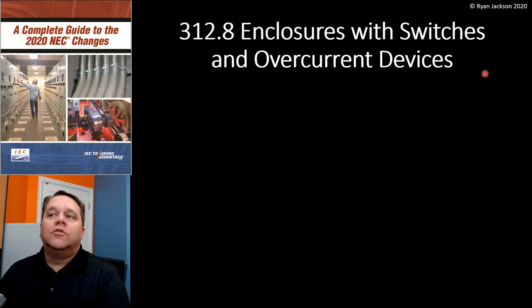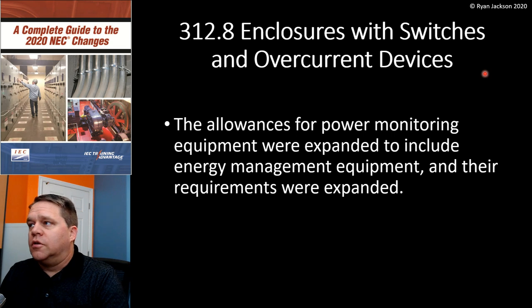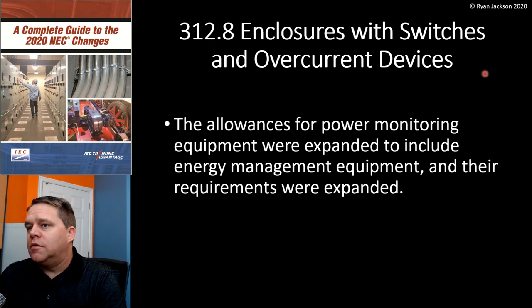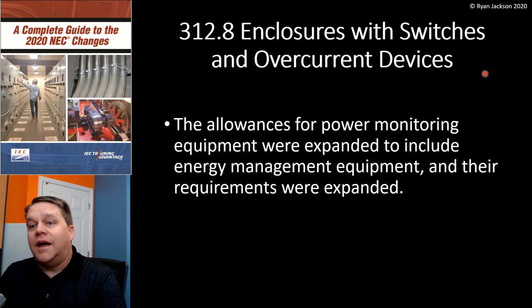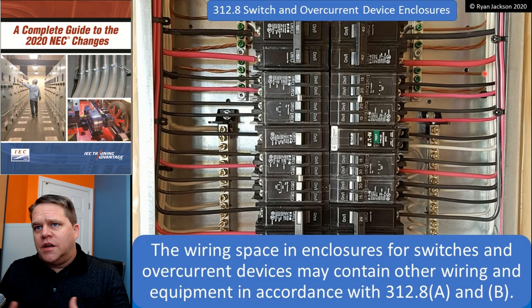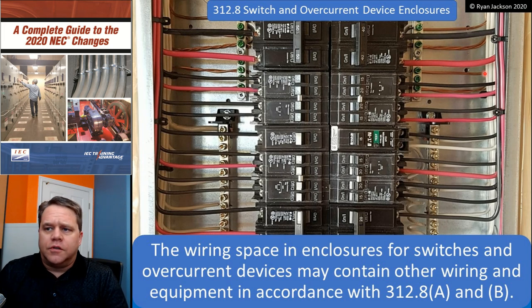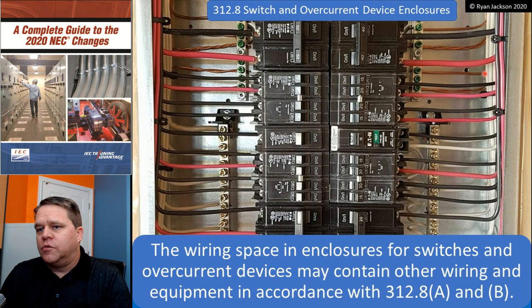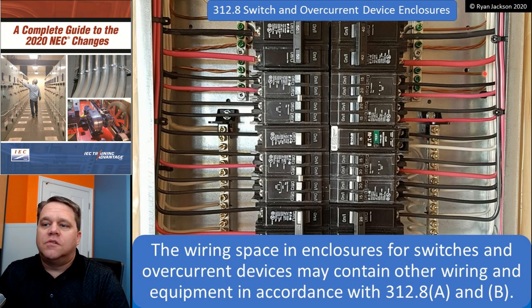Alright, 312.8: Enclosures with Switches and Overcurrent Devices. Small change here — the allowances for power monitoring equipment were expanded to include energy management equipment, and their requirements were expanded as well. We're covering more than just the change because 312.8 is a pretty small section, so let's look at the whole thing. It starts out by saying that the wiring space in enclosures for switches and overcurrent devices may contain other wiring and equipment in accordance with 312.8(A) and (B).